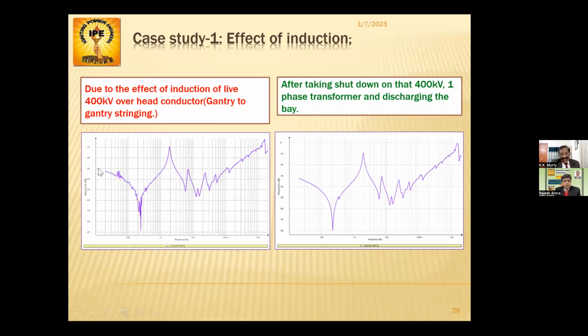One is this, you can see the noise here. This is due to the effect of induction of the live 400 kV overhead conductor, gantry to gantry stringing. See, another transformer is being commissioned just underneath the gantry to gantry stringing of single phase transformers. This was of course at Indore. After taking shutdown on the 400 kV single phase transformer and discharging the bay, you can see the curve has been smoothened. So this was the first case study, showing how the induction of the substation affects the SFRA.